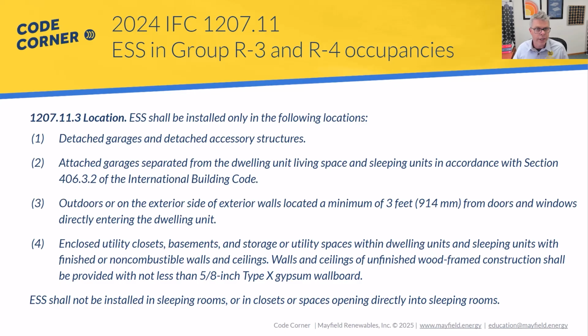And then number 4 is the one that I think gets a lot of attention, and unfortunately is definitely open to some interpretation. I have been talking with people about this, trying to see how folks are interpreting this. You can see that we have these locations where we can install it, and the second sentence talks about if you have unfinished wood frame construction, then you have to provide this 5/8 inch Type X gypsum board to protect the interior of that structure.